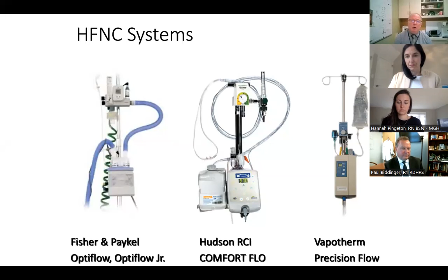So these are the size cannulas we use. We use a pediatric and an infant size cannula. And people are asking, what's the ideal flow rate? For a while, we didn't really know. We used to use estimates like, it should be 3 times the patient's minute ventilation. I don't know what the patient's minute ventilation is. It should meet or exceed their inspiratory demand. I don't really know what their inspiratory demand is either.